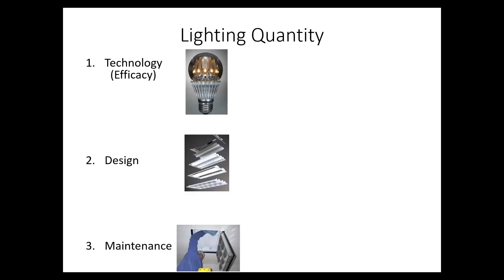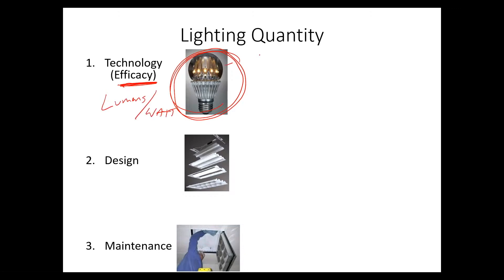Regarding lighting quantity, light emanates from some device, some type of technology. This can be LED, fluorescent, or incandescent. What we're interested in there is the efficacy, which is the lumens per watt. Lumens are what is coming out of the bulb, and the watt is the energy going into the bulb. So we want to get a high efficacy — it's a lot like efficiency, but it's not unitless; it's lumens per watt. We want to maximize that.